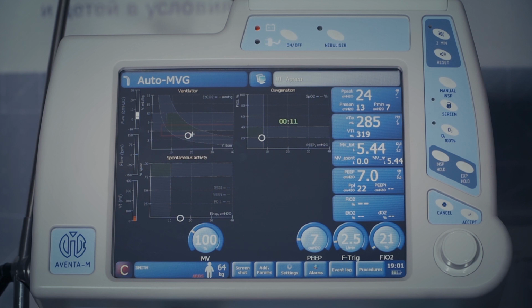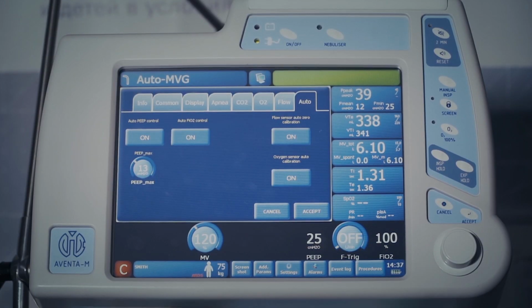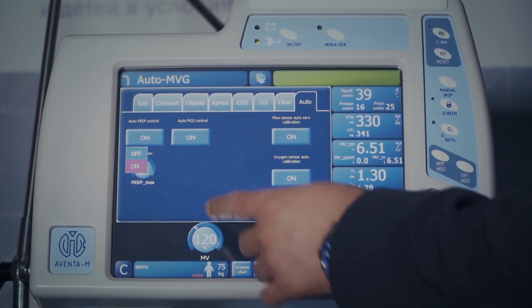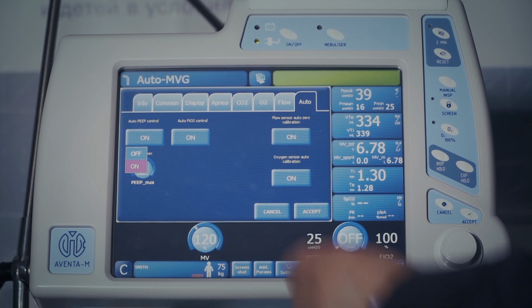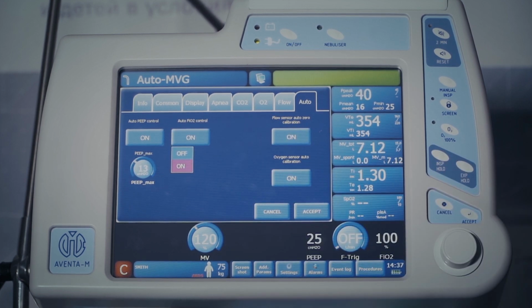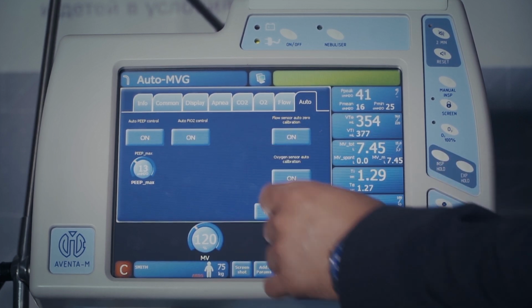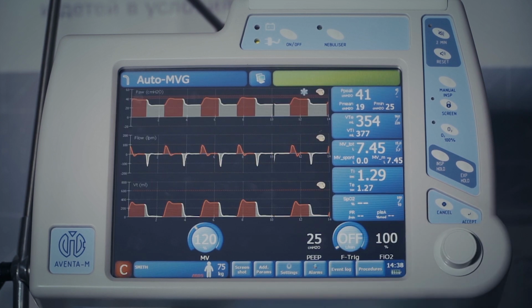When changing the respiratory mechanics parameters or adjusting the preset minute volume, all calculations are updated and the ventilator readjusts ventilation settings to new conditions. One of the most advanced options is automatic adjustment by the ventilator of PEEP parameters and percentage of supplied oxygen in accordance with International Ventilation Protocol ARDS-NET.